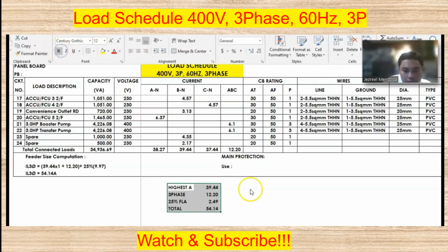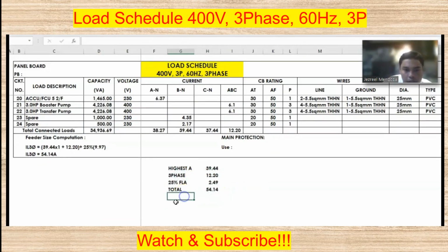And then to get the feeder conductor, we have this I feeder. Let's multiply this total current times 1.25, and then we get 67.69 amperes.